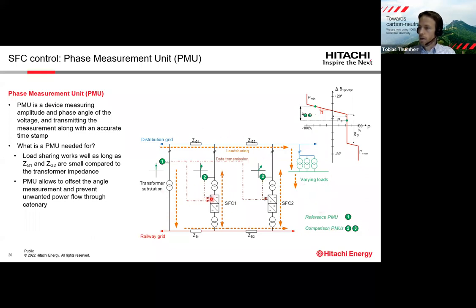You can see here in the example that a railway line is fed with a transformer and 2 static frequency converters in parallel. There is a distribution grid, so we have an impedance in the distribution grid. We have an impedance in the catenary between the different substations, and there is also power flow in the distribution grid towards other varying loads.